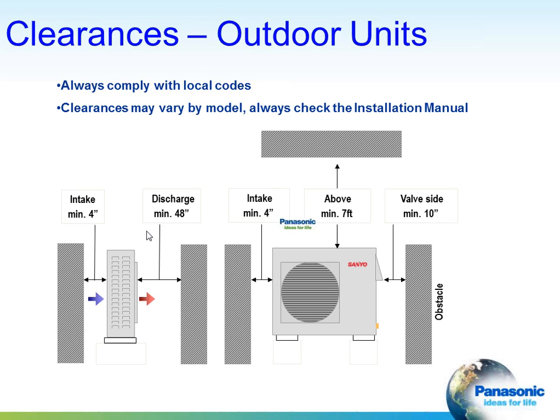Clearances. As with any condensing unit or heat pump, you do have to provide certain clearances for proper operation of the equipment. This would be in the installation instructions, but this just gives you a general idea how much room you need. On the discharge side, you need to stay 48 inches away from any obstructions, and there's also requirements for a minimum clearance above the unit.